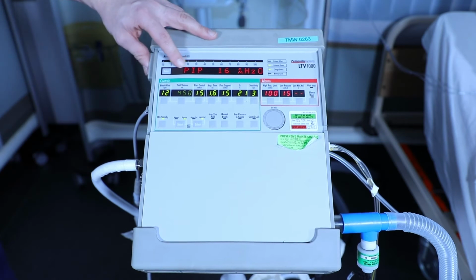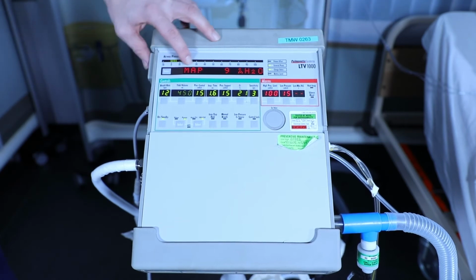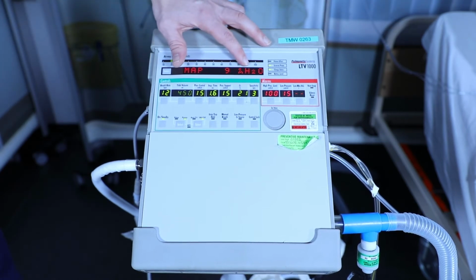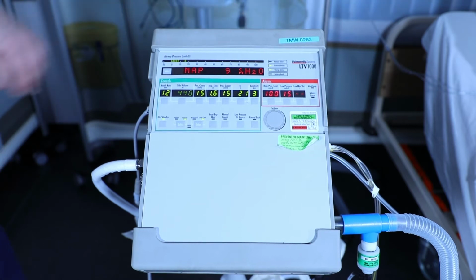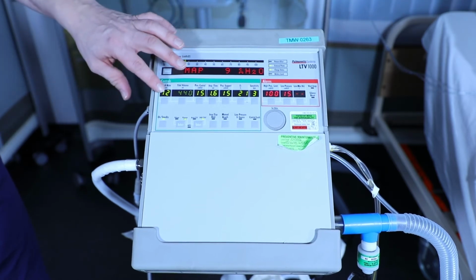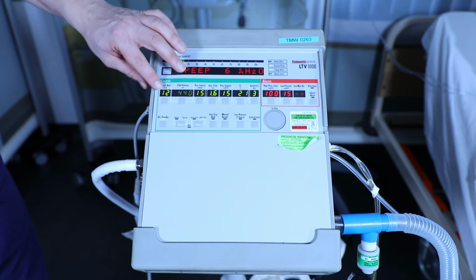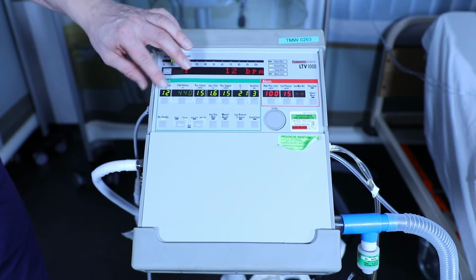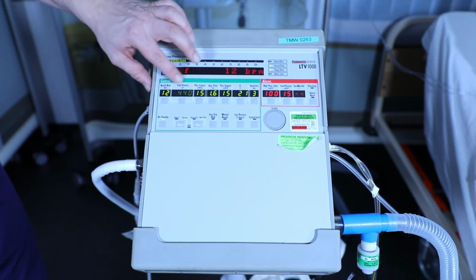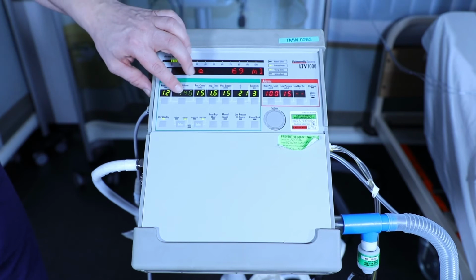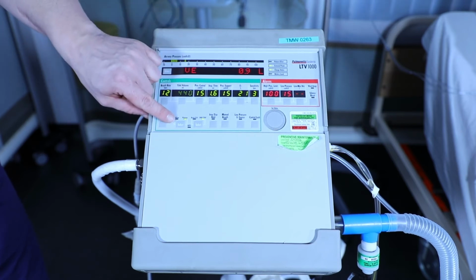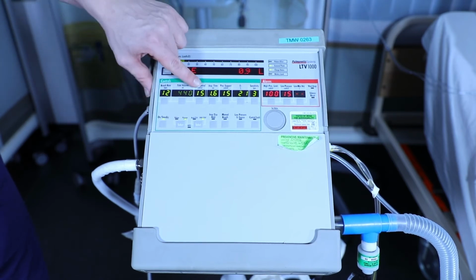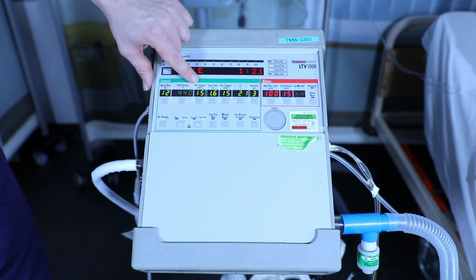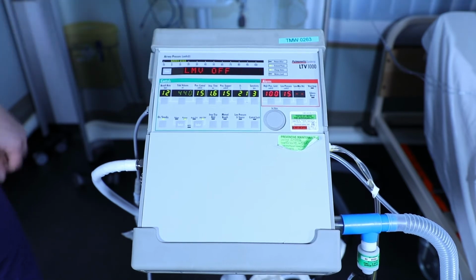We can see here the display screen scrolls through all the parameters. So we can see on the control buttons that some of the LEDs are lit brightly and some are dimmed. The reason why the tidal volume is dimly lit is because this mode is a pressure mode. The tidal volume will be achieved by selecting the pressures.